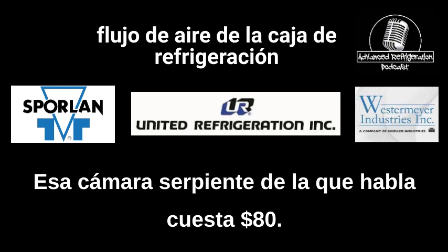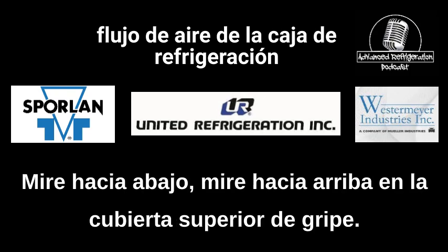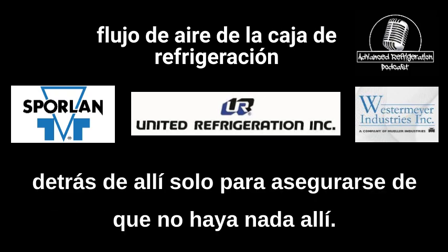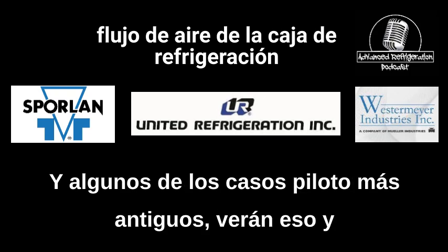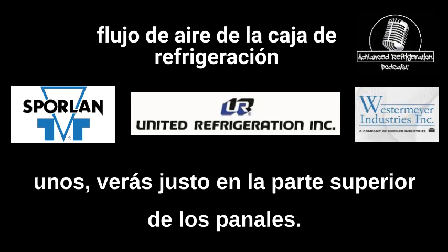That snake camera he's talking about is $80. Pop out one of the access plates in the back, look down, look up. The top flue deck, I call it a flue deck, there's other names for it, but check up in there, behind there, just to make sure there's nothing there. The normal spot, like you said, is right behind the fan motors in some of the older Tyler cases. And some of the ones you'll see, like in the Hussmann ones, you'll see right in the top of the honeycombs.